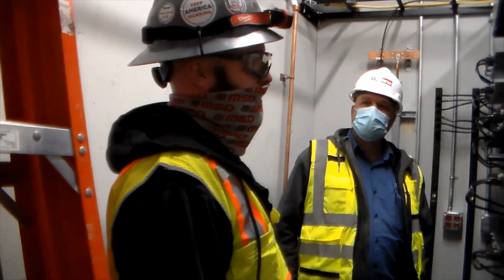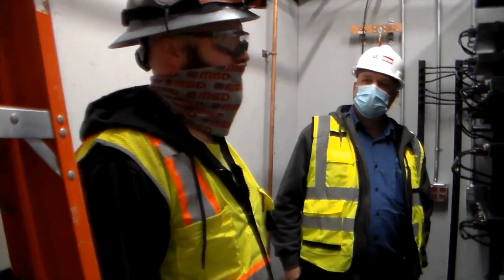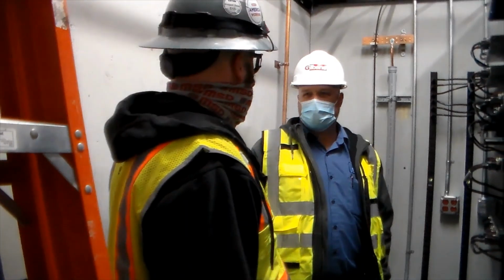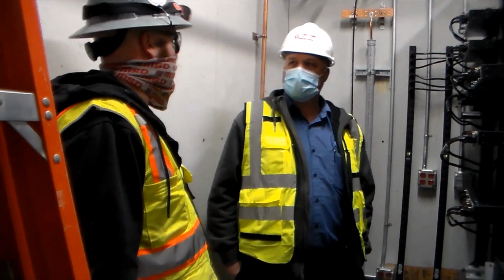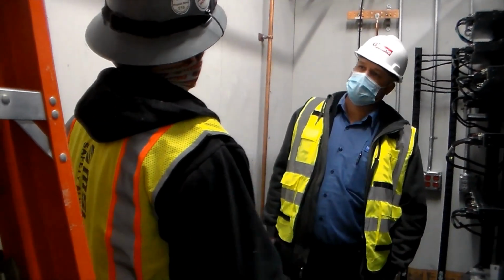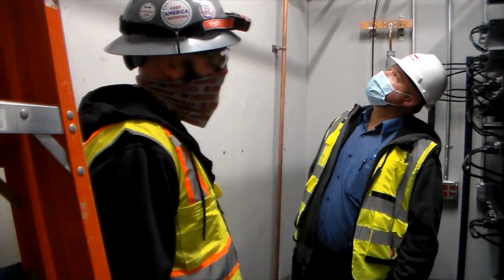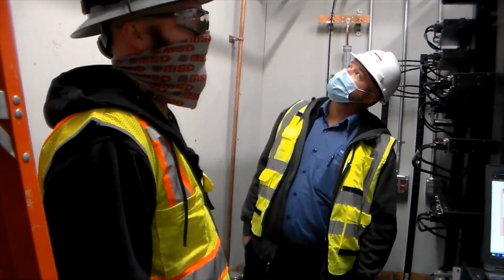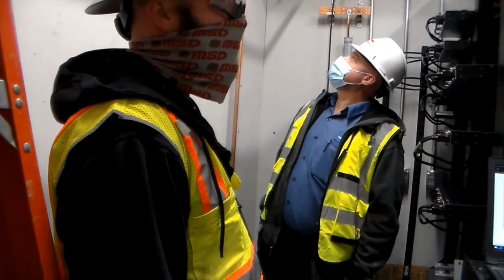And the only maintenance issue would be obviously cleaning your condenser coils and your filter, but these are pretty simple units to maintain. A nice unit to put in a room like this. It really is. It's just going to be a matter of how much heat's generated off this. Mitsubishis or Daikin, those are the top two in my opinion. There's enough concrete here it shouldn't really be struggling in this room. The concrete will hold the cool temperature for you.